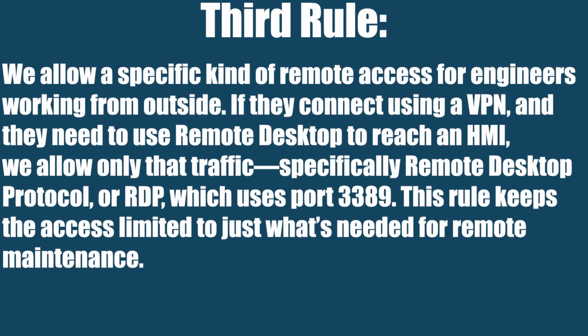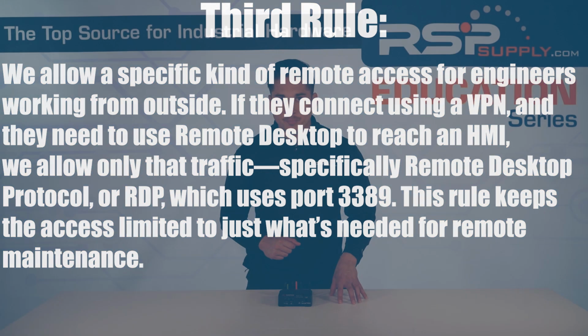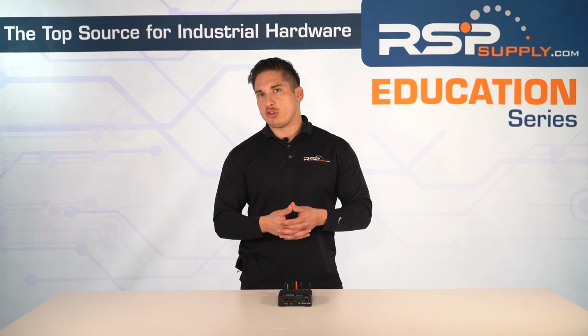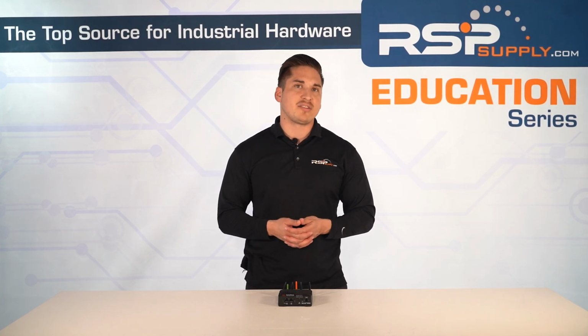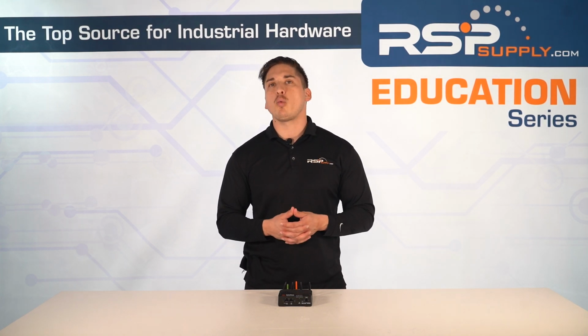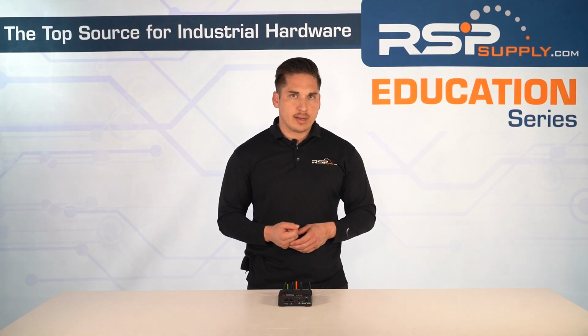A third rule might be, we allow a specific kind of remote access for engineers working from outside. If they connect using a VPN and they need to use remote desktop to reach an HMI, we allow only that traffic, specifically remote desktop protocol, or RDP, which uses port 3389. This rule keeps the access limited to just what's needed for remote maintenance. These are just a few examples, but they show how firewall rules help keep things safe by controlling who can talk to what and only letting in what's absolutely needed.